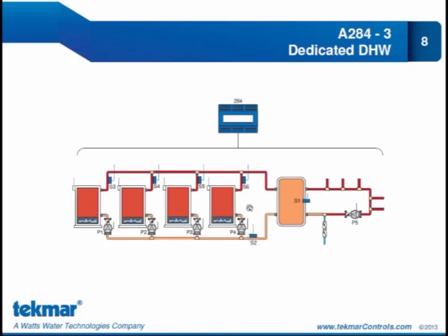Again, we have our boiler inlet sensor, individual boiler outlet sensors so that we can do that delta T across the boilers. This also lets us do a boiler max for each individual boiler. So instead of a max for the system, a new feature for the 284 is to have a boiler max temperature for each boiler. And if we rise above that limit, the 284 will turn that boiler off. So that's another advantage, a new feature to the 284 boiler control.